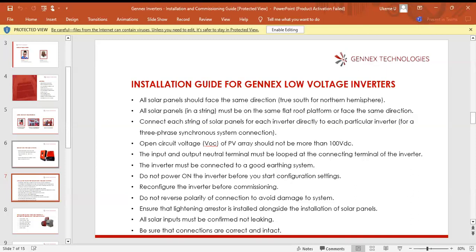Reconfigure the inverter before commissioning. Whether your inverter has gone for repair or is a new system, before commissioning you have to go through the program and make sure the settings inside are correct. You may be relocating the inverter for a reason, and you have already programmed it for the one that's there.